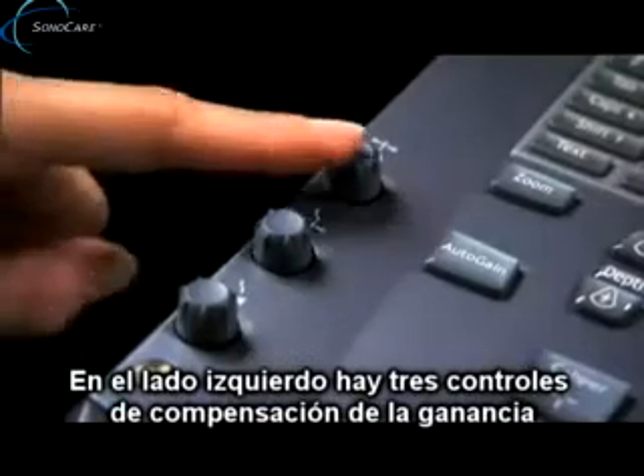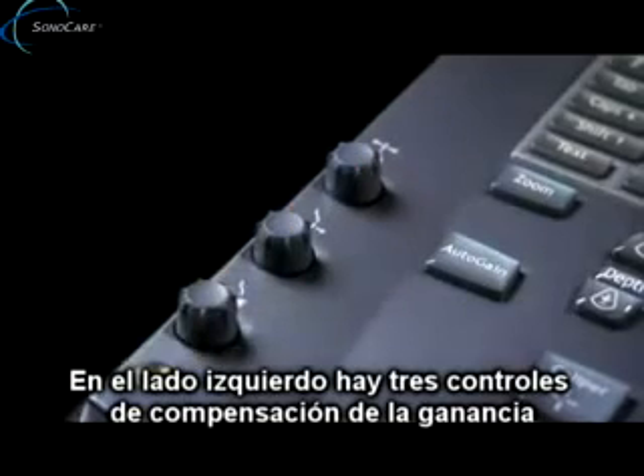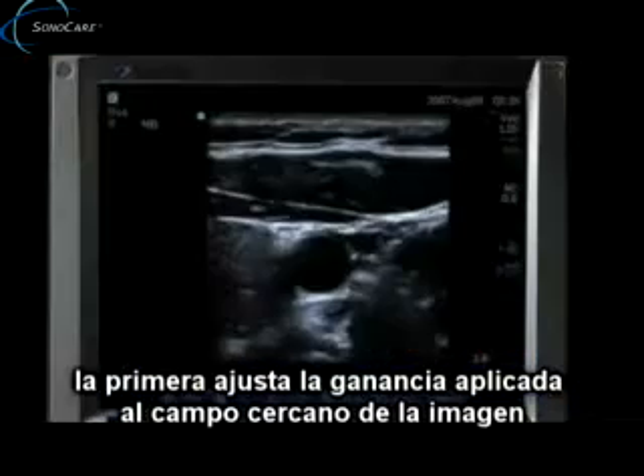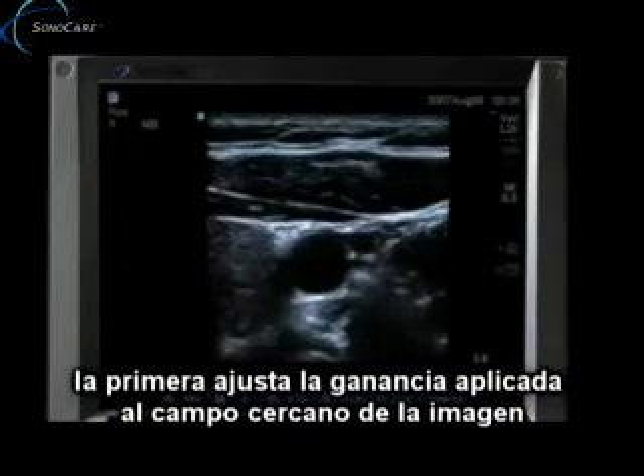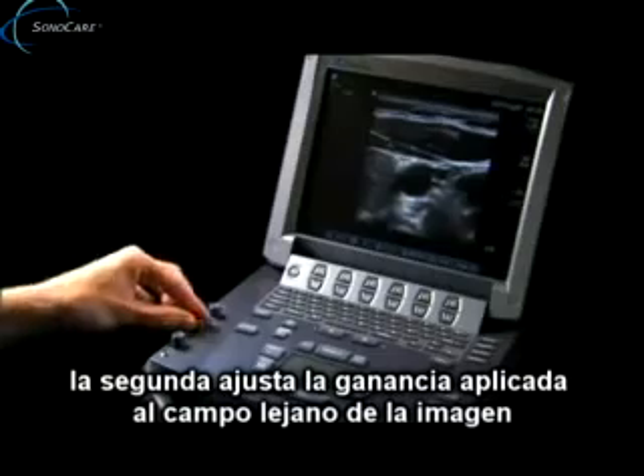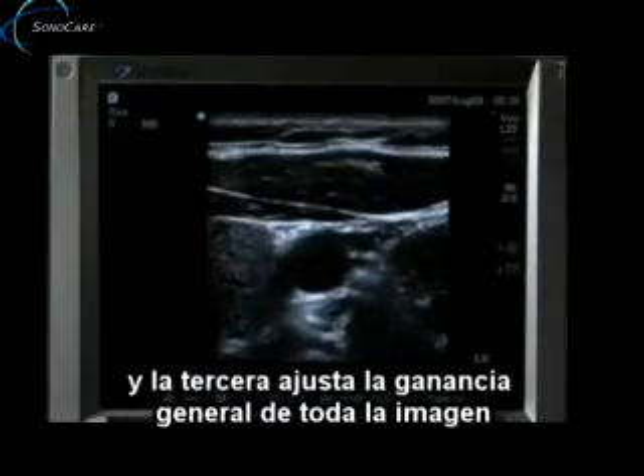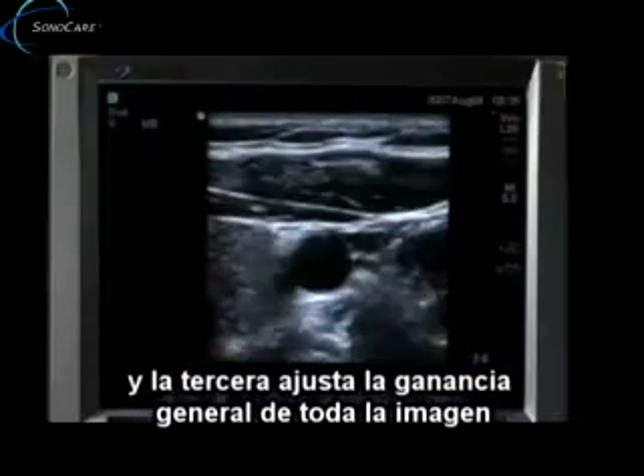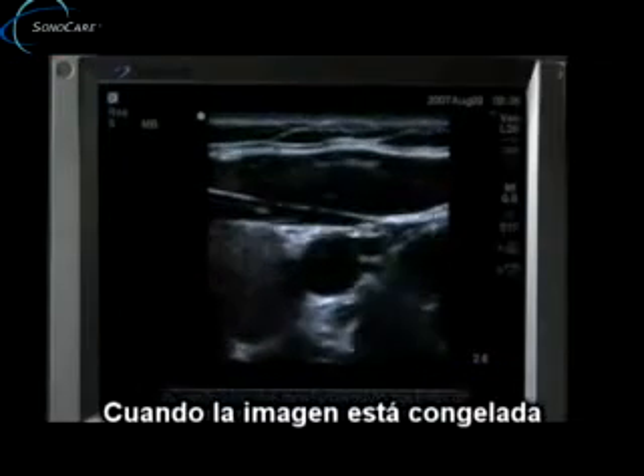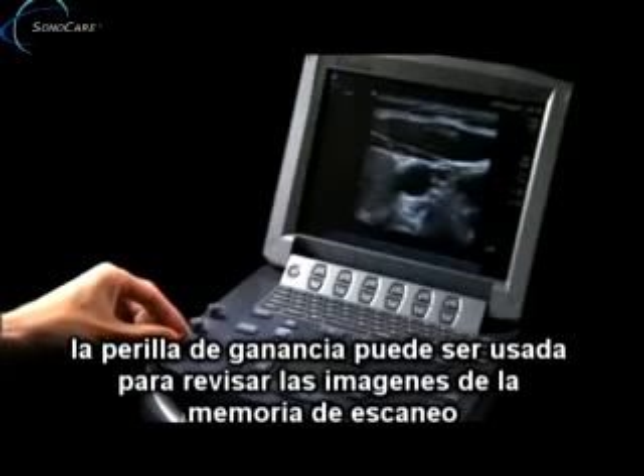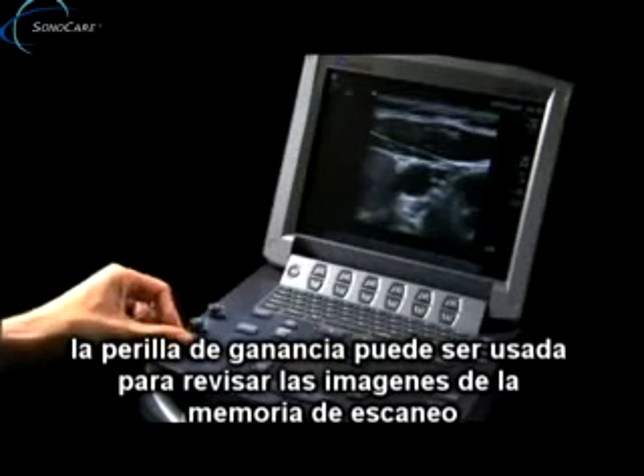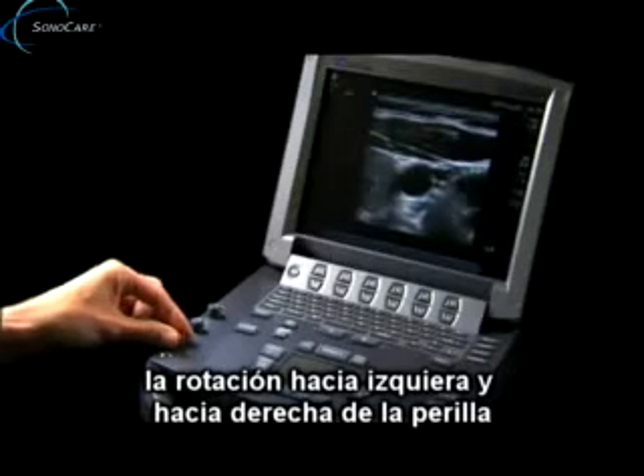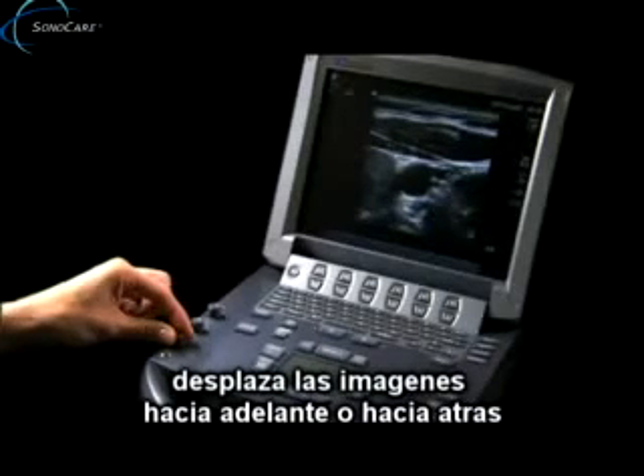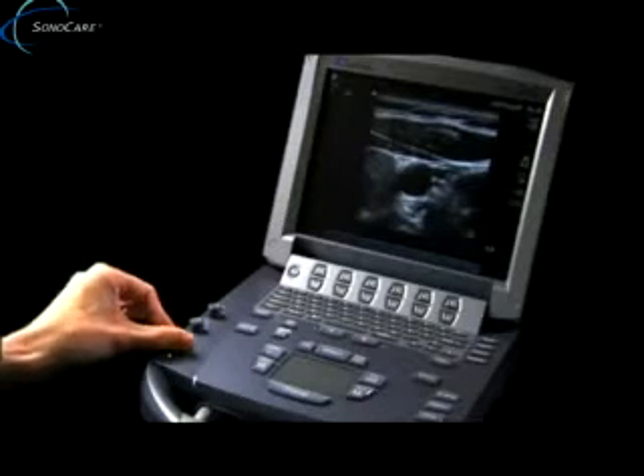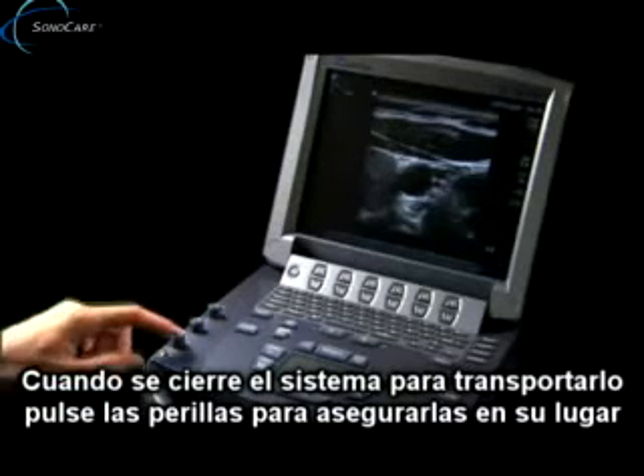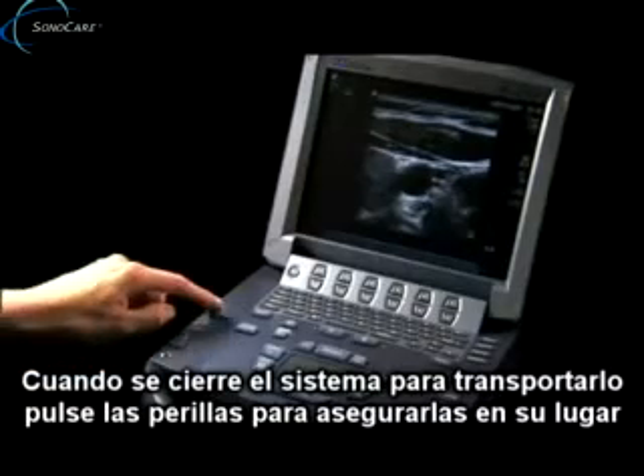On the left-hand side, there are 3 controls for gain compensation. Near adjusts the gain applied to the near field of the image. Far adjusts the gain applied to the far field of the image, and gain adjusts the overall gain applied to the entire image. When an image is frozen, the gain knob can be used to review images in the cine buffer. Counterclockwise and clockwise rotation of the knob scrolls backward and forward through the stored images. When you are closing the system for transport, depress the knobs to lock them into place.